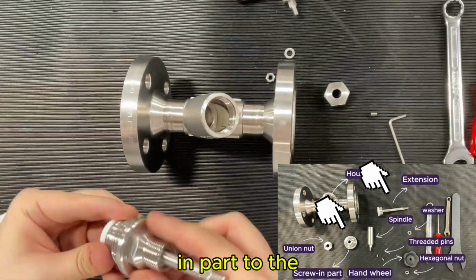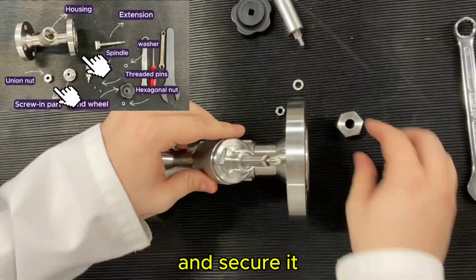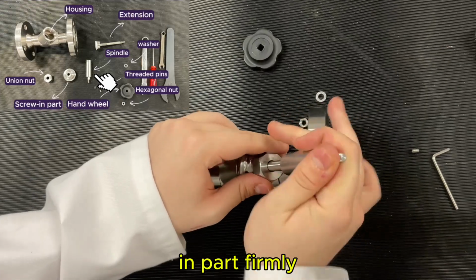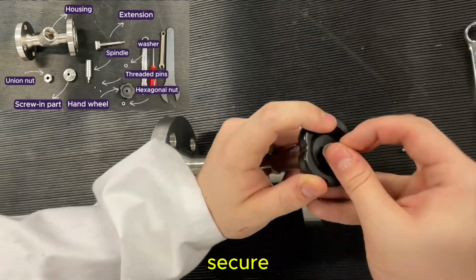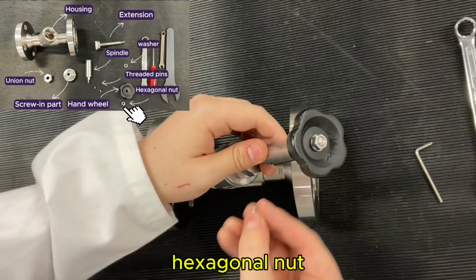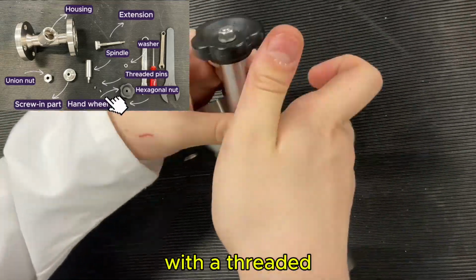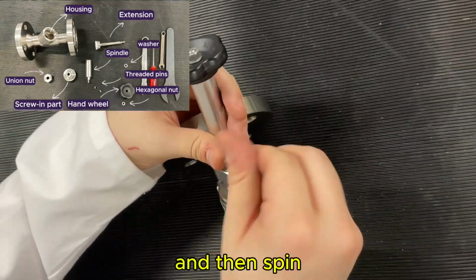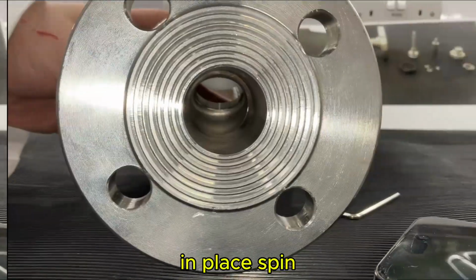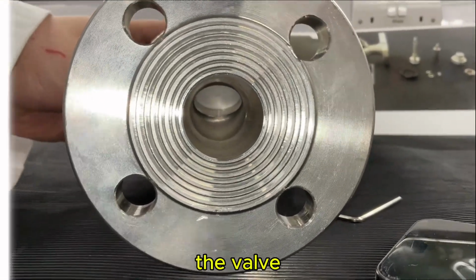Start by connecting the screw-in part to the extension. Screw the extension into the housing and secure it with the union nut. Attach the spindle to the screw-in part firmly and add the handwheel to the spindle. Secure the handwheel in place using the washer followed by the hexagonal nut. Finish by securing the spindle in place with the threaded pins using an Allen wrench. And then spin the spindle to lock it in place. Spin the handwheel to open and close the valve.